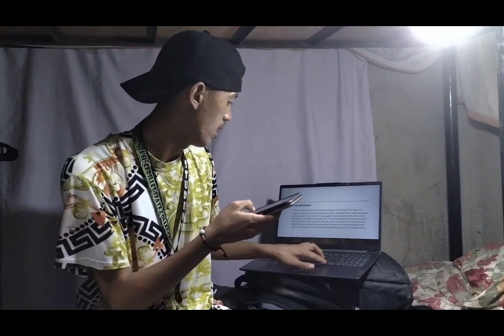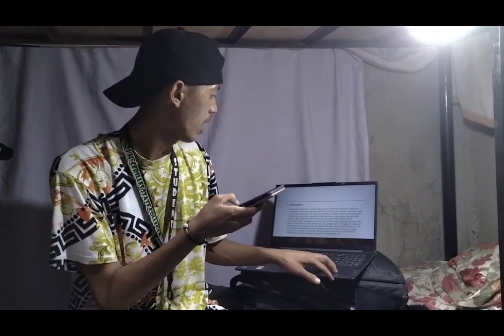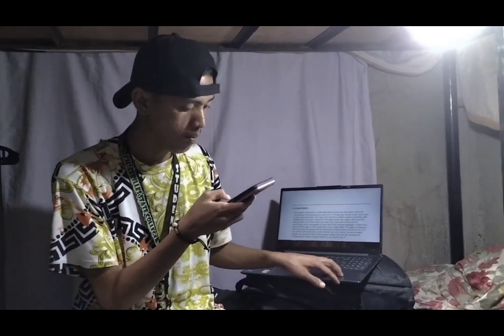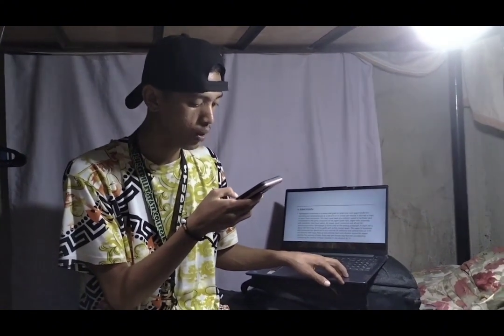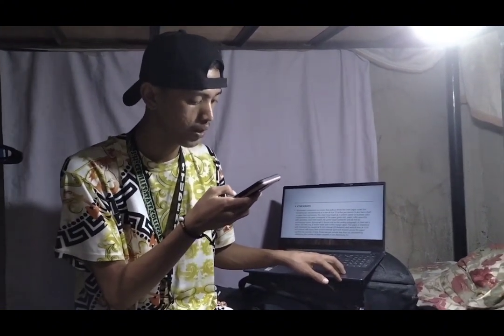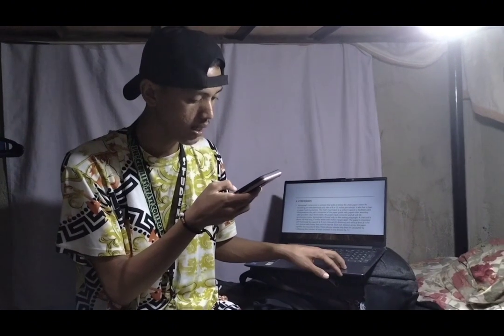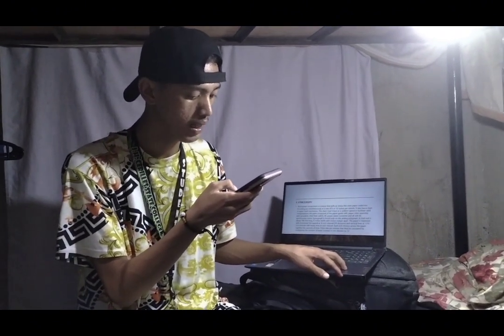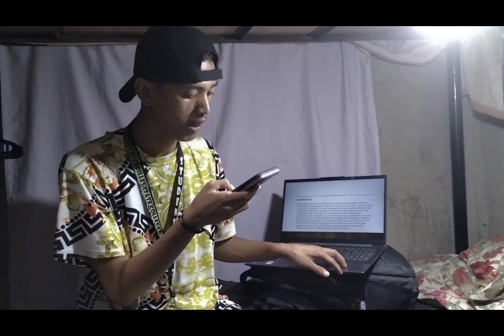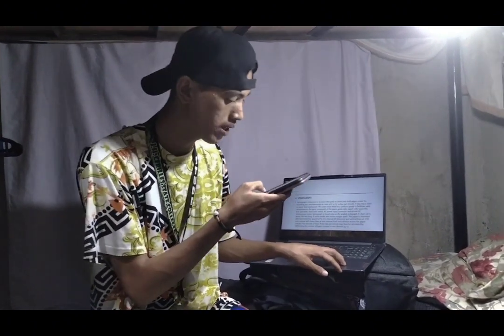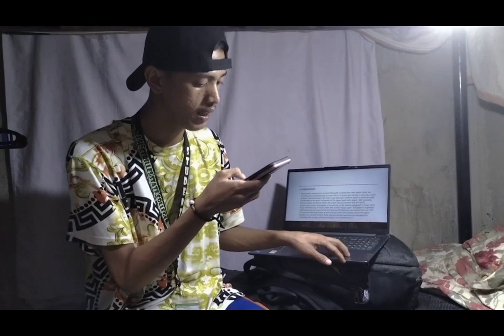Next is number 4, kymograph. The kymograph is a motor that drives the chart paper under the recording pens simultaneously at a rate of 6 to 12 inches per minute. It is also a chart or paper feed mechanism. This chart must travel at a uniform speed to facilitate valid interpretation.